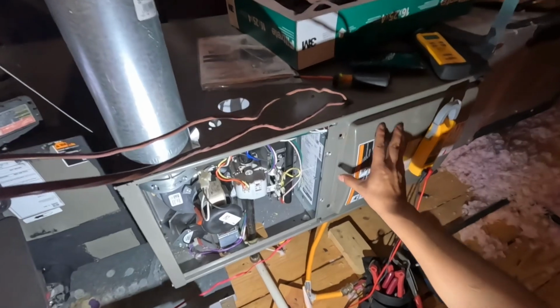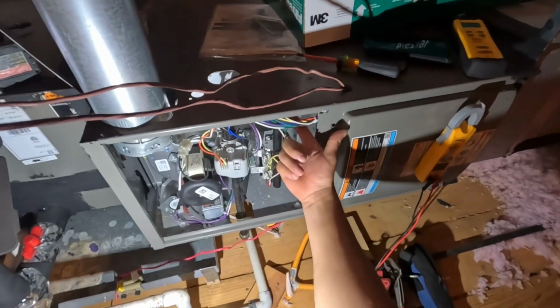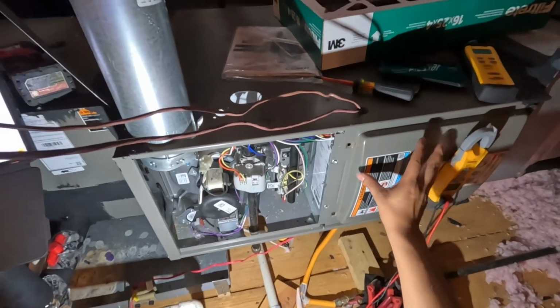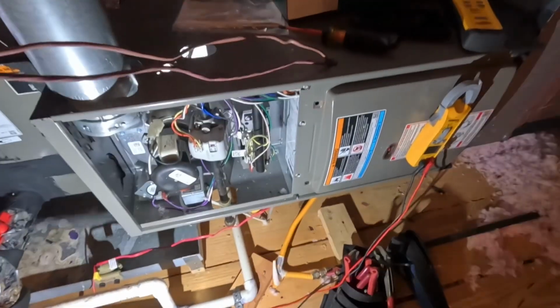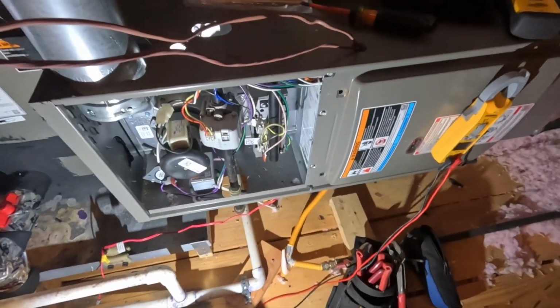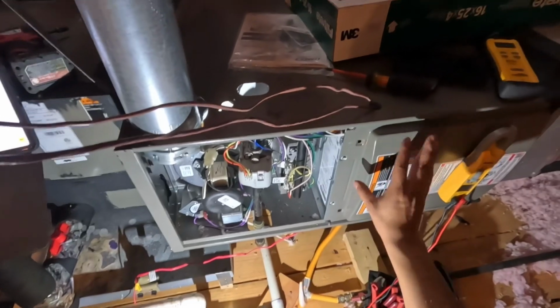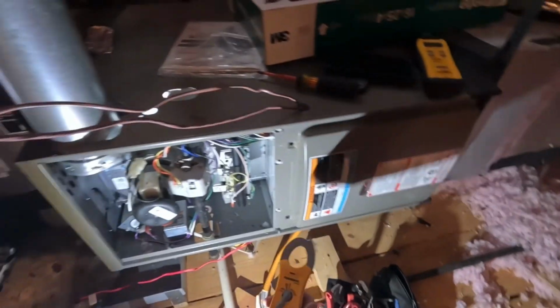It's always better to check the amps through these wires right here, actually taking this panel off and jumping it, because we're not gonna get the true amperages if it's not pushing it through that coil. This here, if we have it off and check it right here, we'll get the true amperages of the motor. So we want to try and get the amperage of the motor while the panel is off.